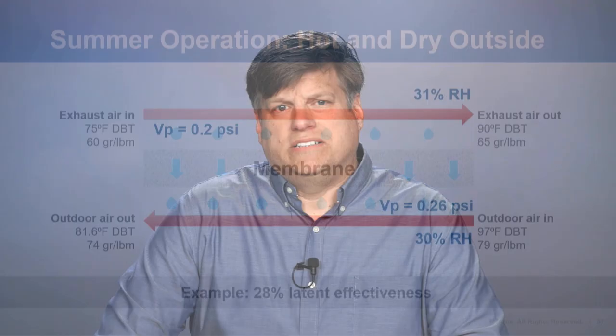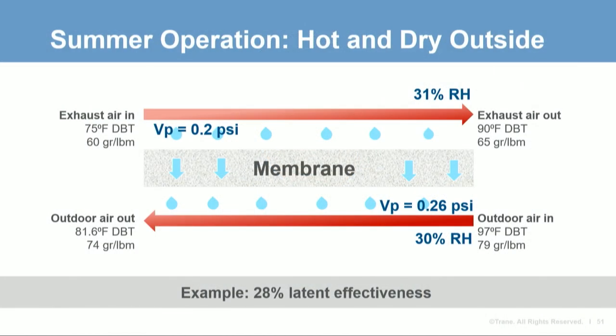During winter heating mode, the latent effectiveness will be highest. When it's hot and dry outside, the latent effectiveness will be lowest, though there is not much humidity to transfer at that condition. The latent effectiveness will be higher during a hot humid day when recovery is needed most versus a hot dry day. The degree of this variance will depend on the membrane used.